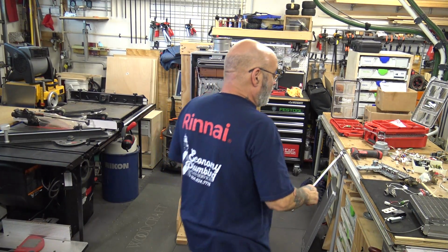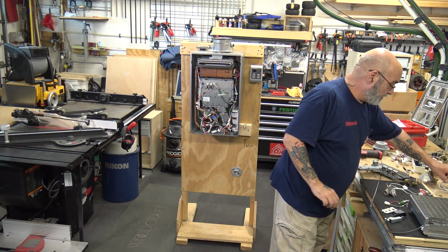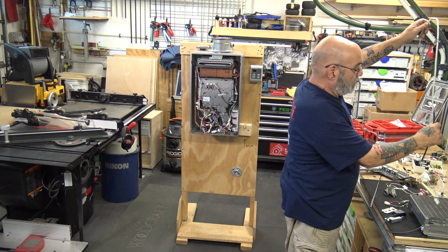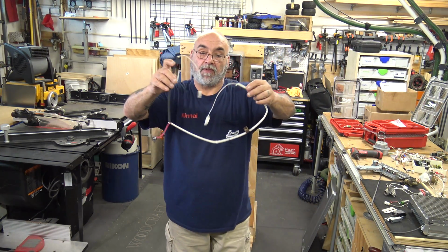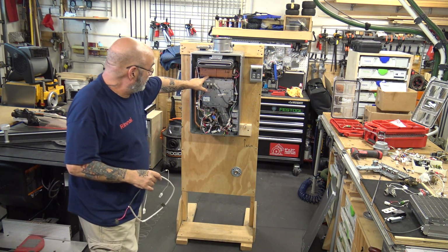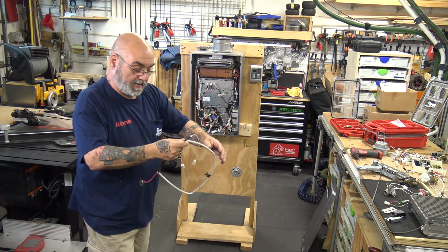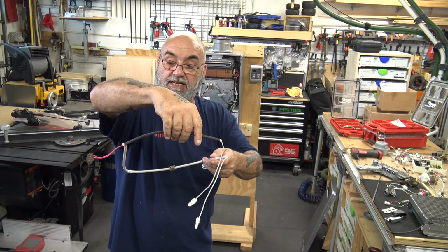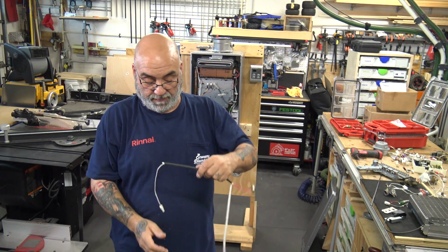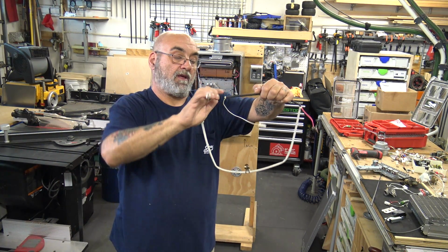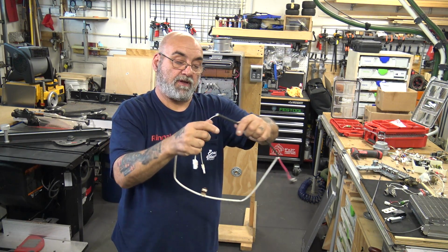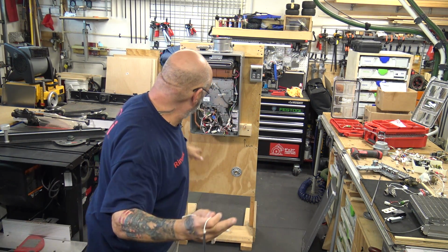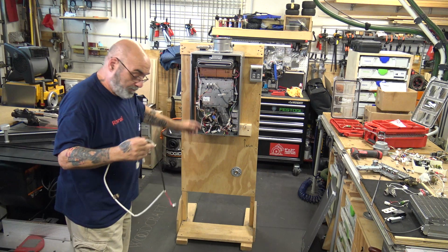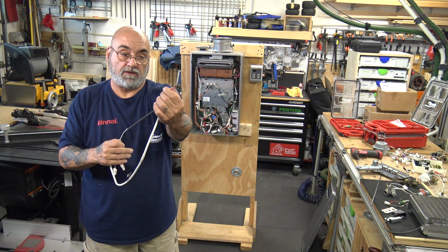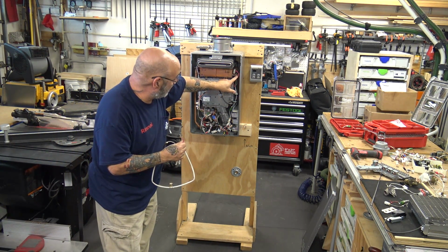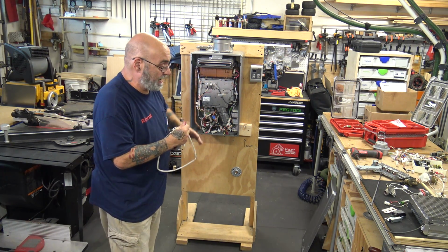Now, you have a couple of safeties on this. You have the thermal fuse that wraps around the heat exchanger. See, you have a black, white, white, and that's what this is. It wraps around the heat exchanger. Actually, it wraps around that way, sorry. It wraps around this way. And these 2 wires right here are going down to here. Then you have this heat sensor, 2 pink wires, which is right here. So that is what's sensing overheating.